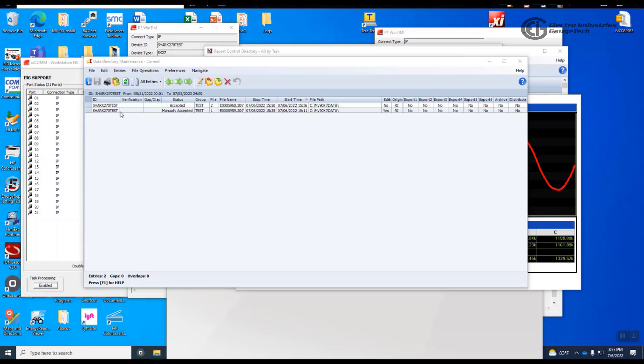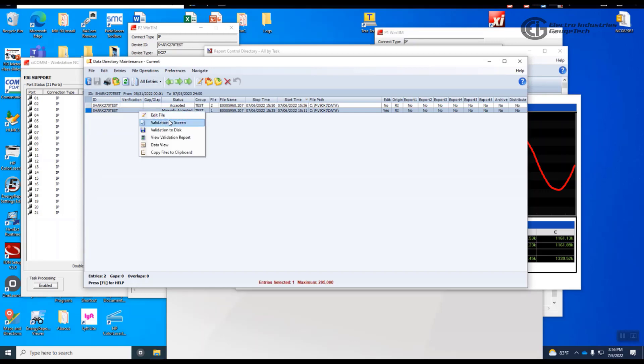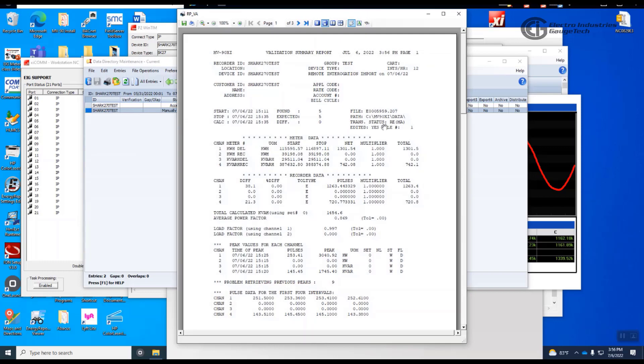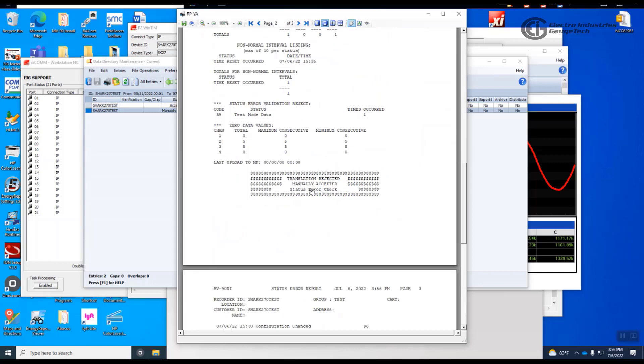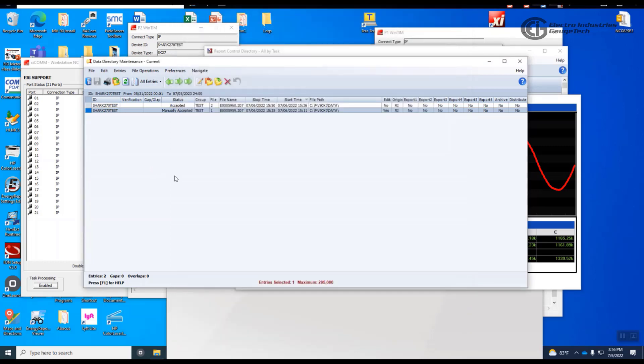Previously we looked at the meter and saw that it would reject because it failed a certain point for validation. Validation is very important to MV90 — it verifies all the different parameters set in the meter. This meter was rejected and you can see it says status 'R' with 'MA' in parentheses in that file, meaning it was manually accepted after being rejected. We're going to take a look at why it failed validation, as this is something customers frequently ask about.